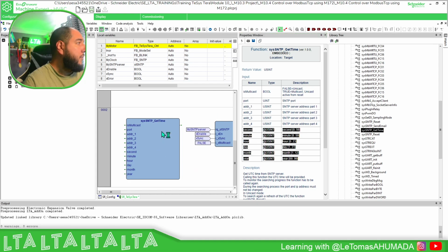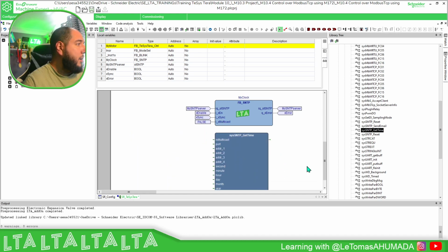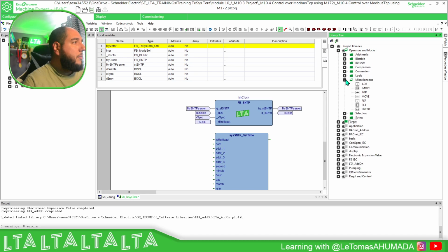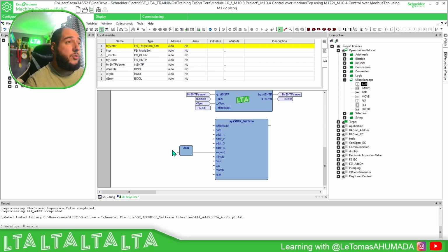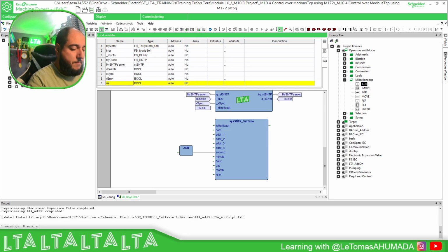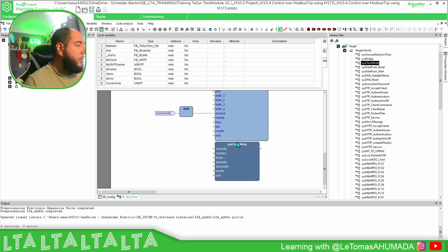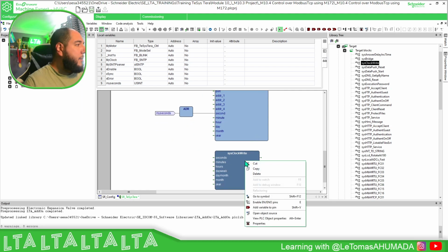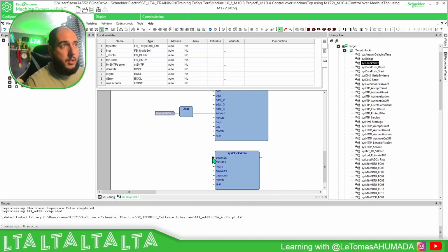In order to get this information with this function block, we use, along with it, the ADR connected here on each of them. So we get the information here. You can create an internal variable, for example, something like myseconds. This one is USINT. Once you get this information, you just use sys clock write. Of course, not at the same time, unless you use the enable and chain the enables together. Then use this one, my second, over here. This is how you need to work.